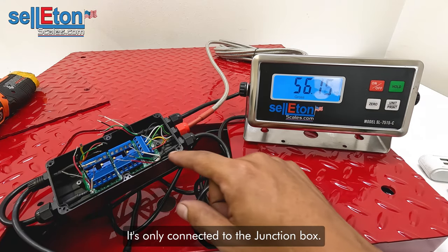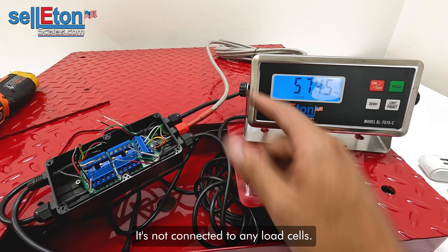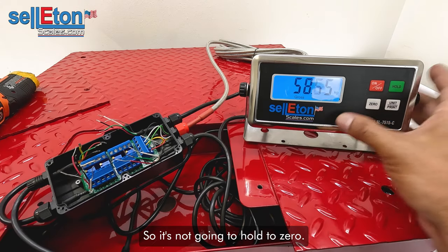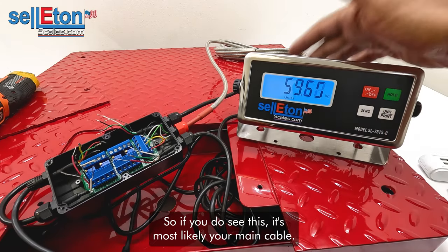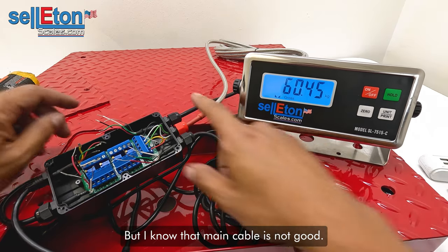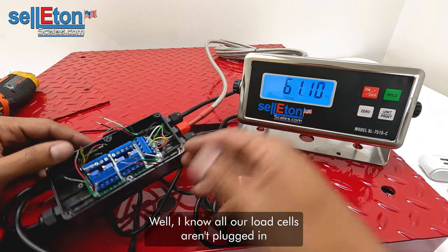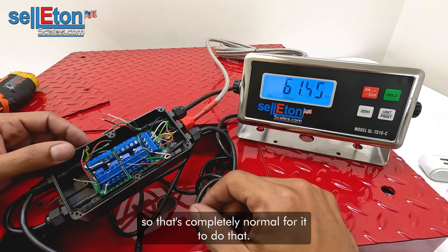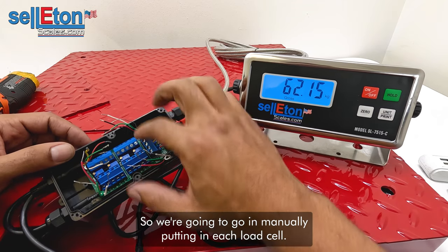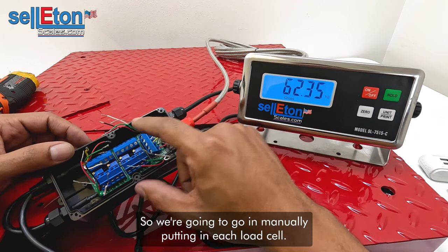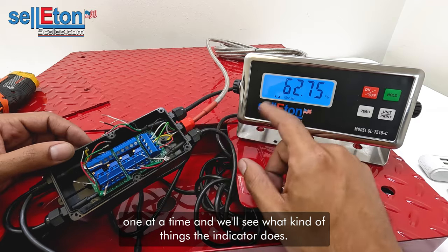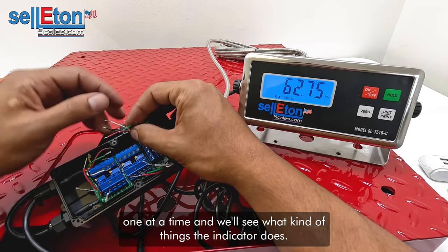When an indicator does that, that means you're not connected to anything. It's only connected to the J-box. It's not connected to any load cells, so it's not going to hold the 0. So if you do see this, it's most likely your main cable. But I know the main cable is not good. Well, I know all our load cells aren't plugged in, so that's completely normal for it to do that. So we're going to go in manually, putting in each load cell one at a time, and we'll see what kind of things the indicator does.